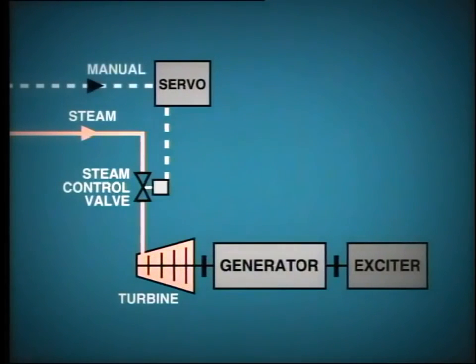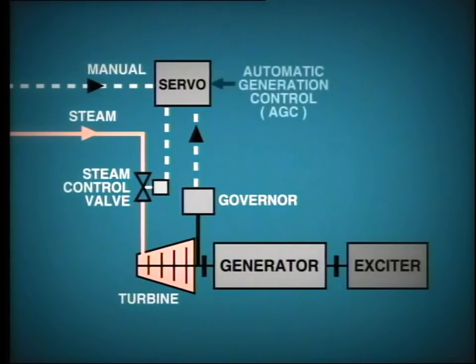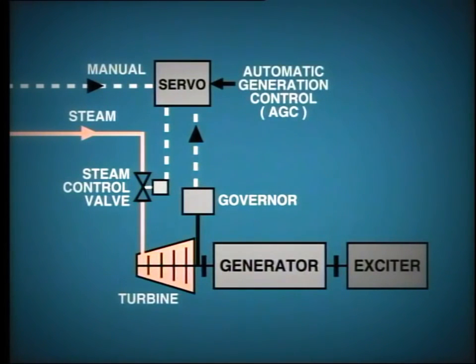Manually by the operator in accordance with predetermined loading instructions or on request from the dispatcher. Automatically by the turbine governor, which responds to changes in turbine speed, which is in turn related to system frequency. Automatically by the dispatcher's AGC, if this particular generator is being used for regulation, that is, to assist in frequency control.